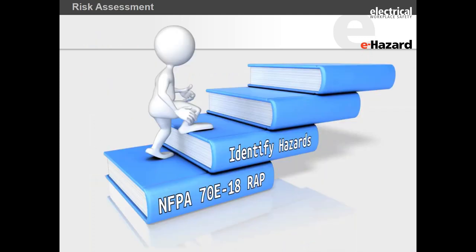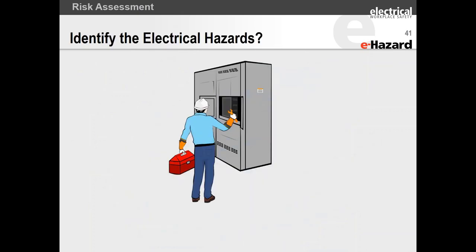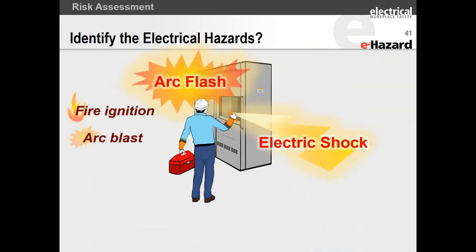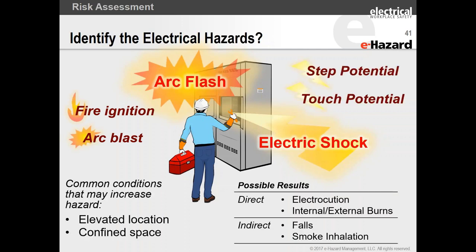Identification of hazards is so important. In a quality job plan and job briefing, you need to clearly identify the hazards: direct contact, touch potentials, shock potential — quantified and clearly documented for each specific task. In incident investigations when people get hurt, they often find that people didn't even really identify the hazards, which is step one in a risk assessment procedure.